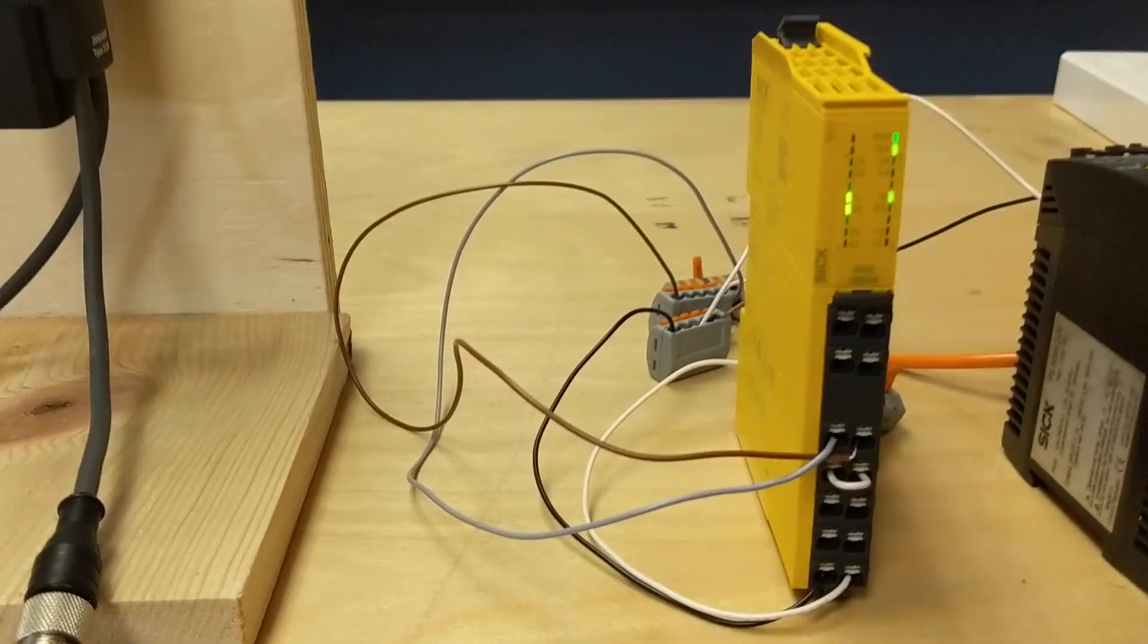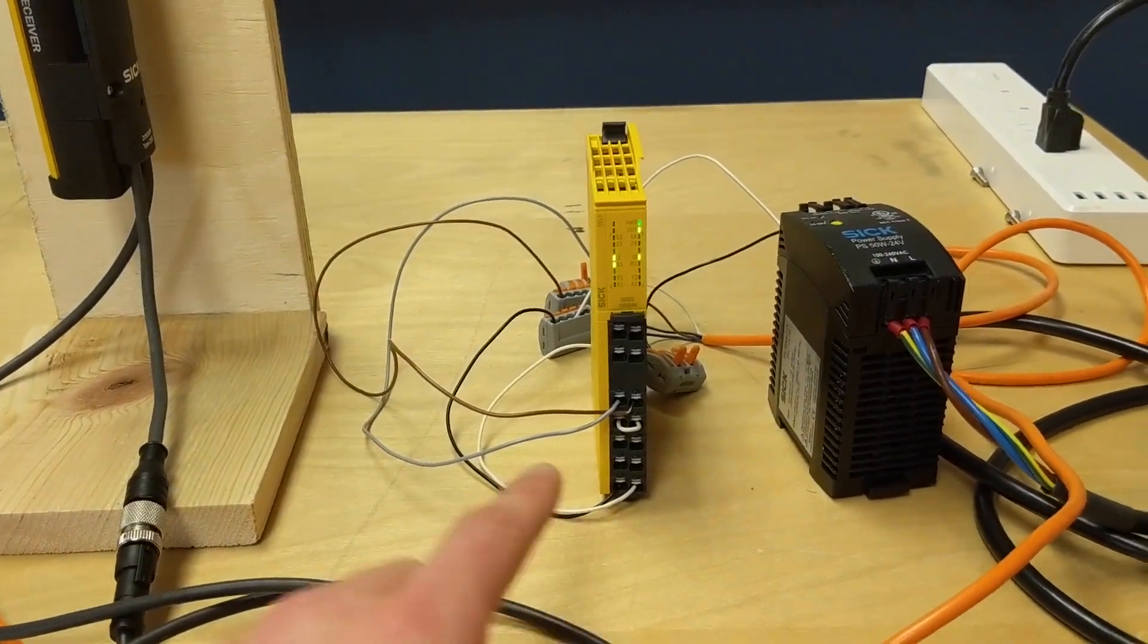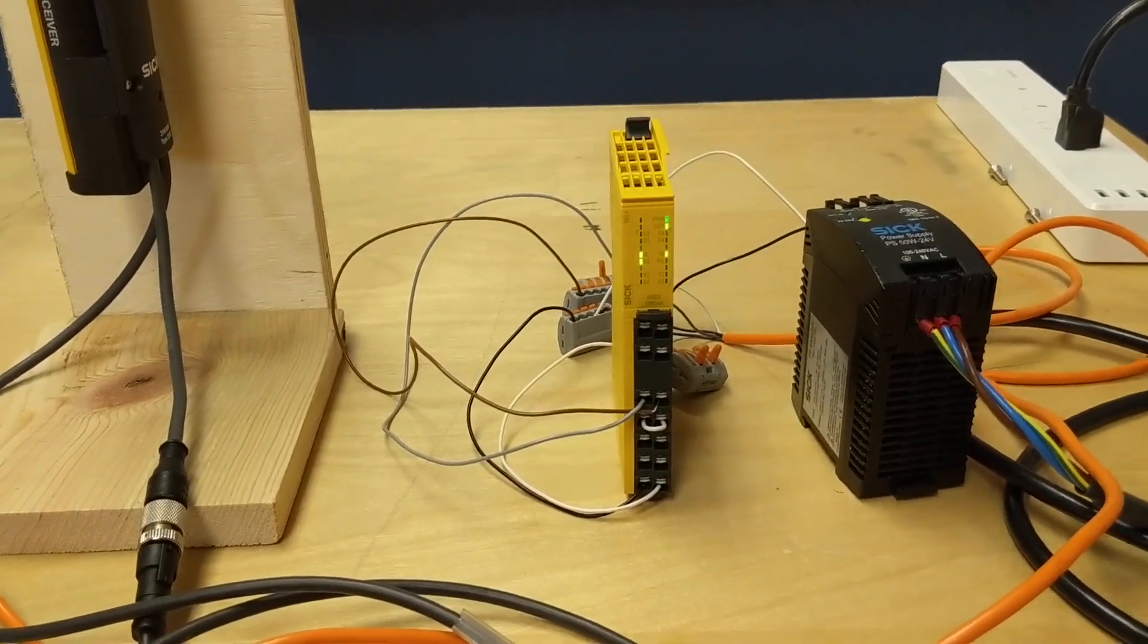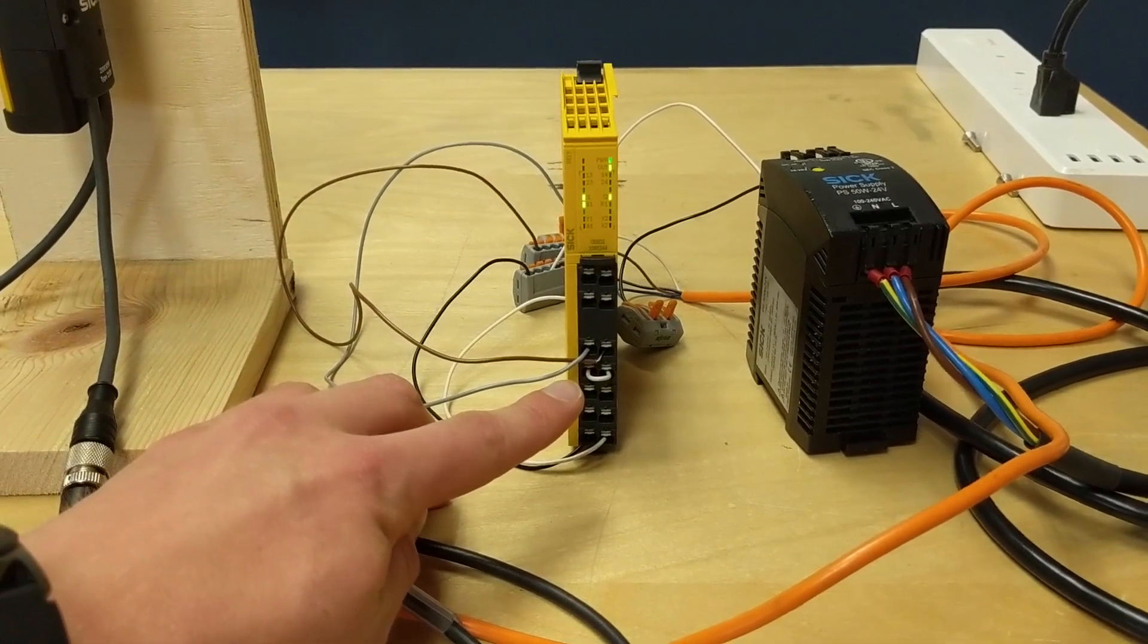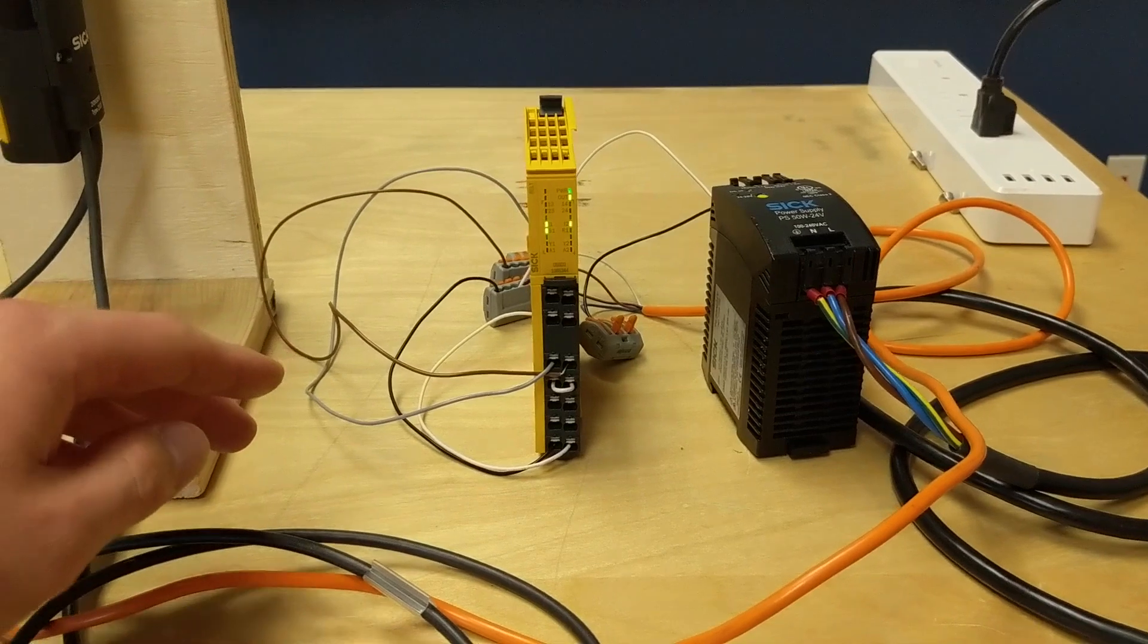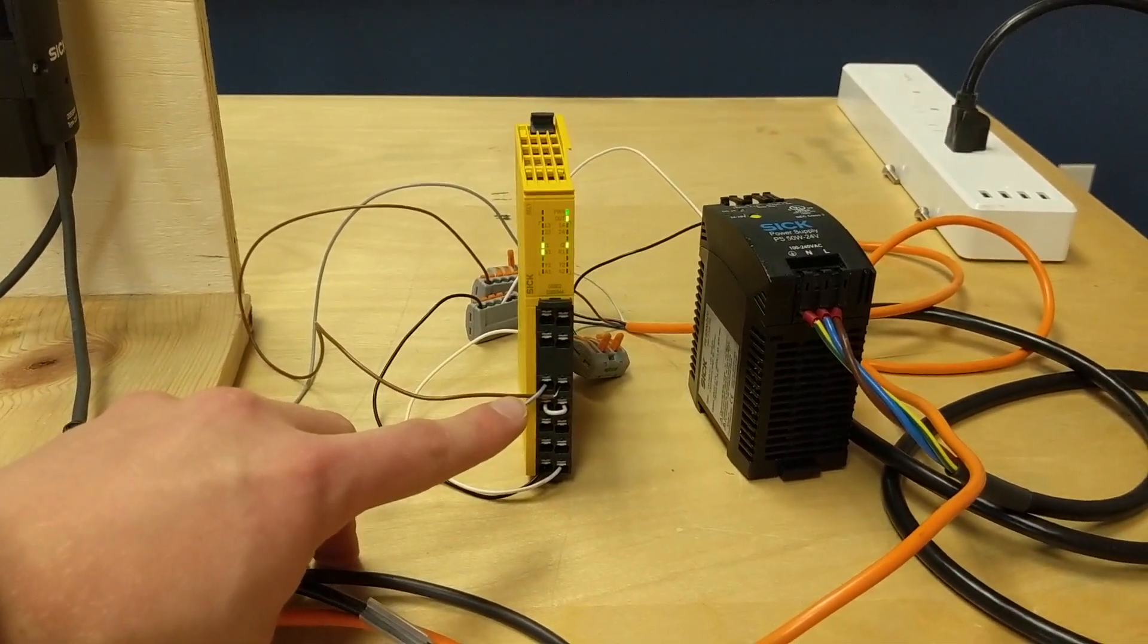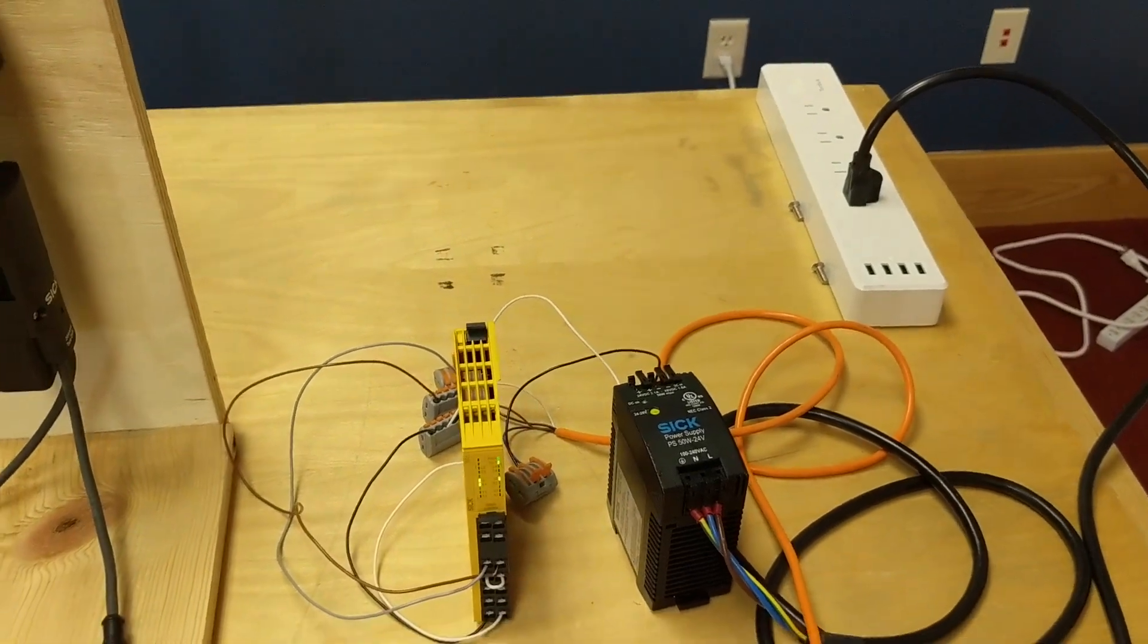As you can see, I have the A1 and A2 hooked up to 24 volts and 0 volts respectively. Then I have a jumper between S1 and R1 for an automatic reset within the safety relay, and I have both safety inputs I1 and I2 connected to the OSSD wires of the cable.